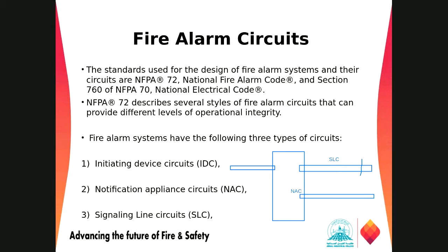So in the SLC, normally we connect all those devices which detect the fire: smoke detectors, heat detectors, manual call points, pull stations, duct detectors, and so on. Once the SLC detects a fire, it will give a signal to the fire alarm panel, and then the fire alarm panel will activate the alarm system.